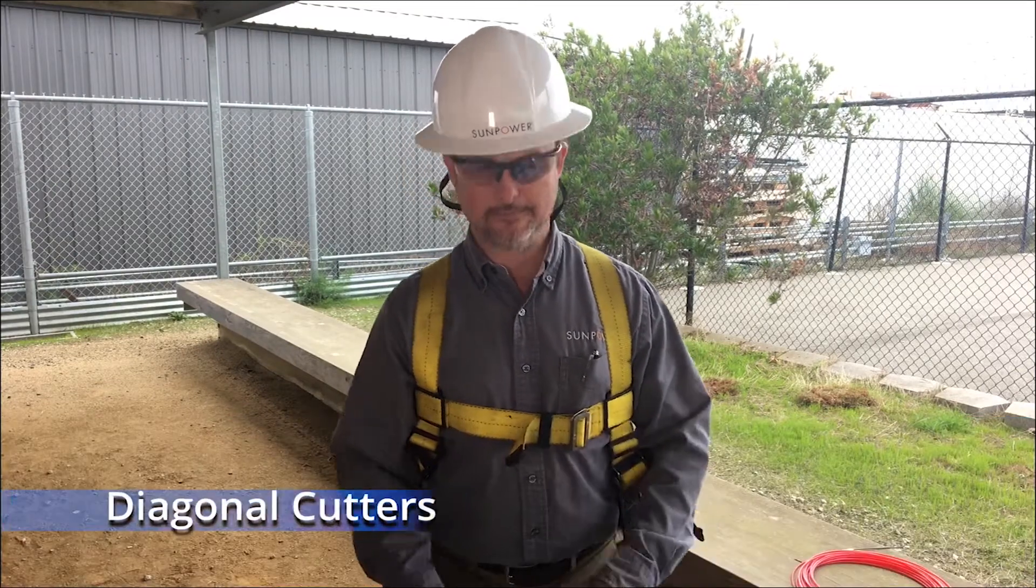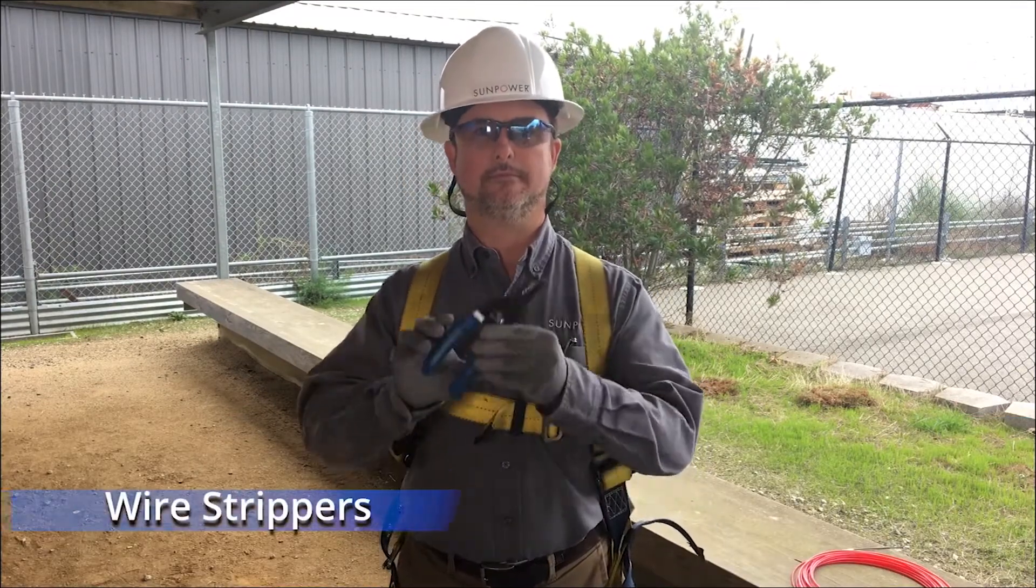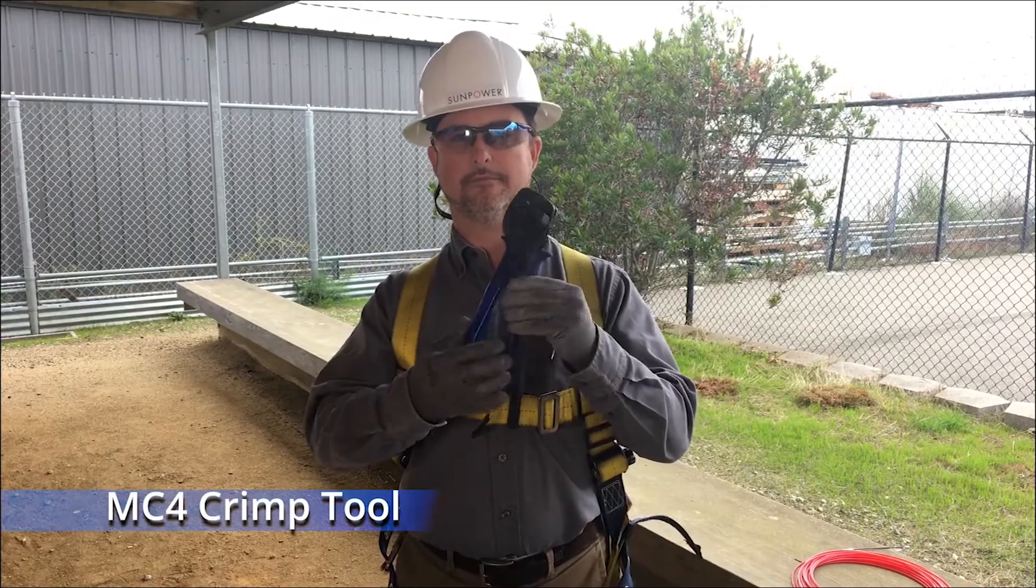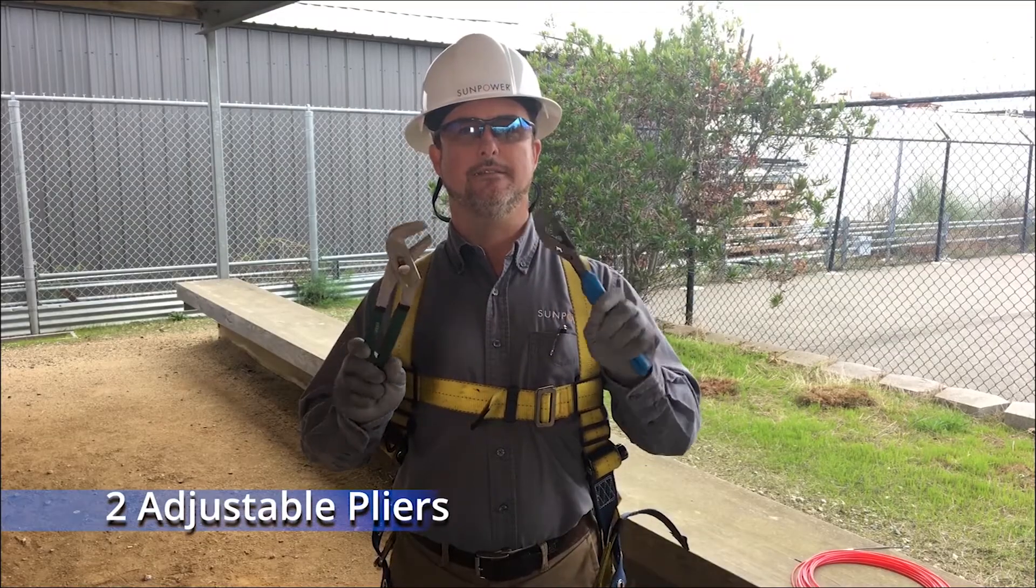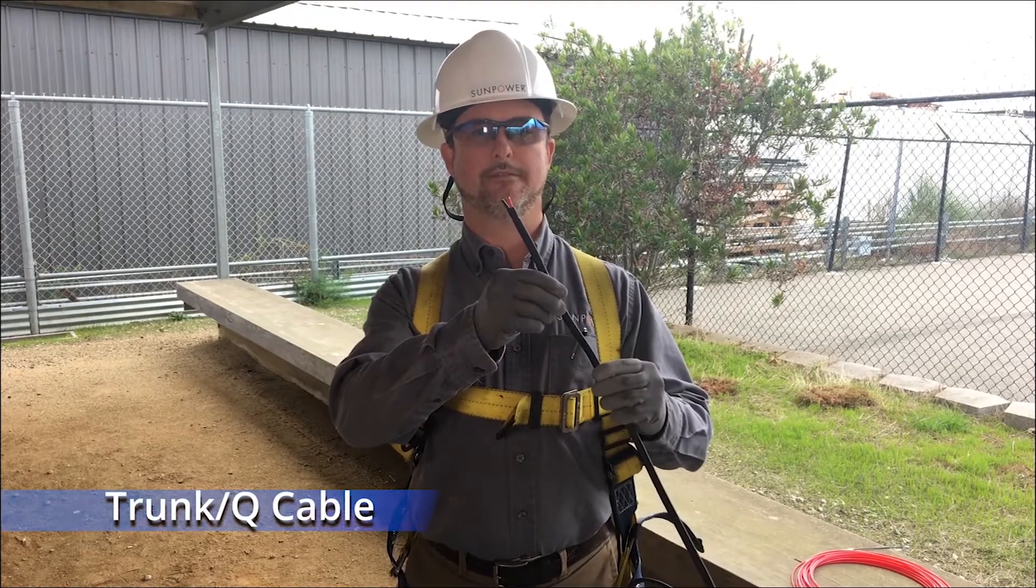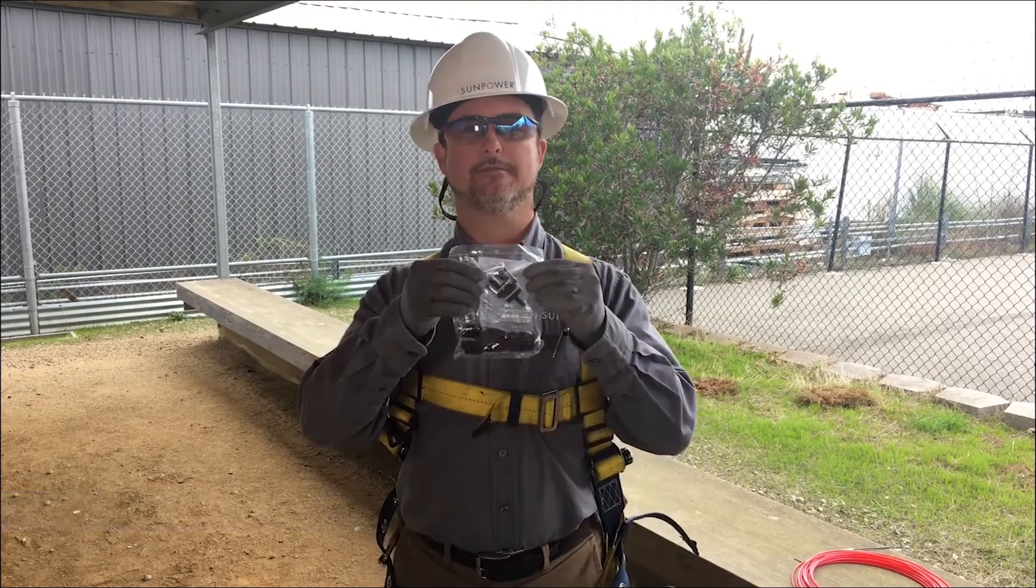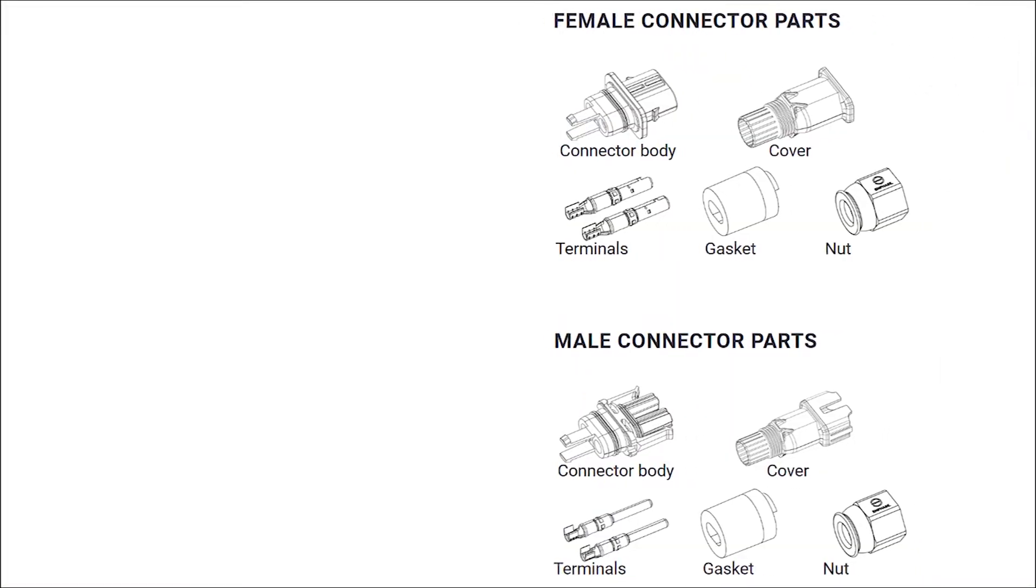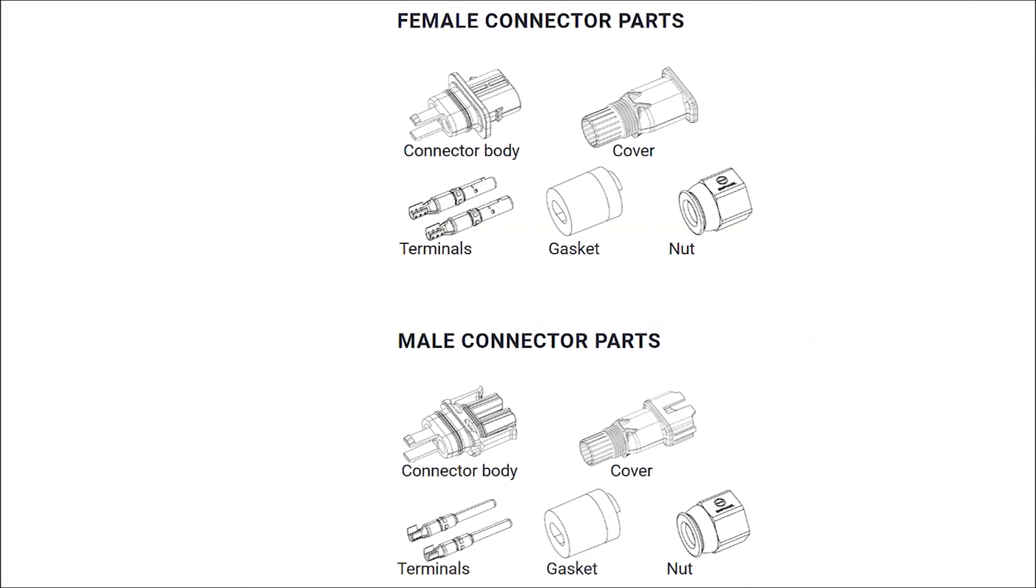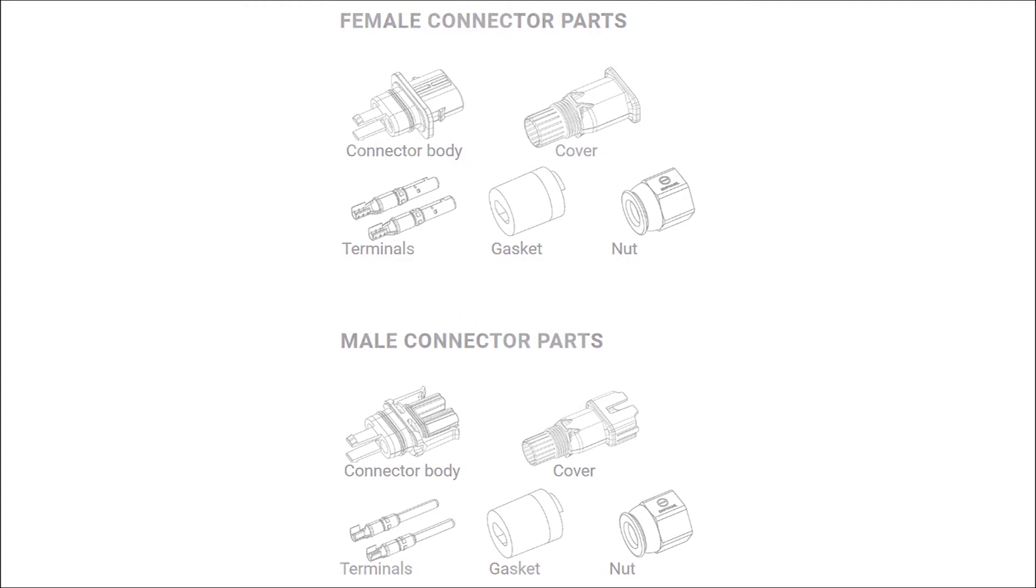You'll need diagonal cutters, wire strippers, an MC4 crimp tool, a disconnect tool, two adjustable pliers, manufacturer-approved cable, and a razor knife, plus a field-wirable connector kit which consists of a connector body, cover, terminals, a gasket, and a nut.